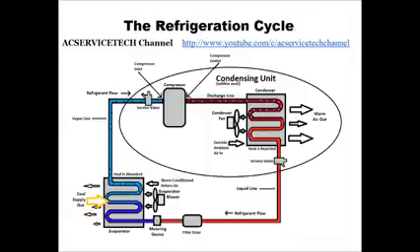Until it comes out of the evaporator coil, it's still absorbing heat. As it comes out of the evaporator coil, the temperature increase from the end of the saturated state in vapor to where it comes out is called the superheat. If you continue along, you keep coming up as a low pressure, low temperature vapor, you make a right, and you come over to the service valve. That's where we take a superheat reading.